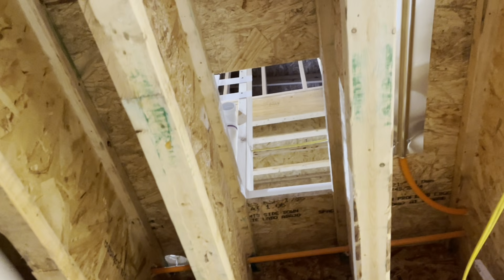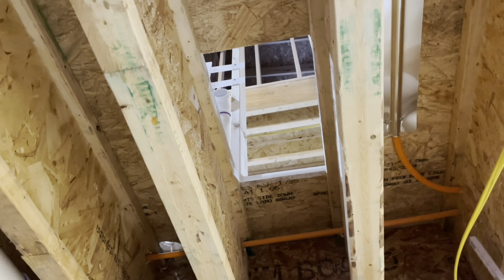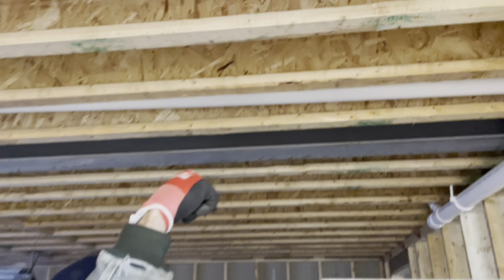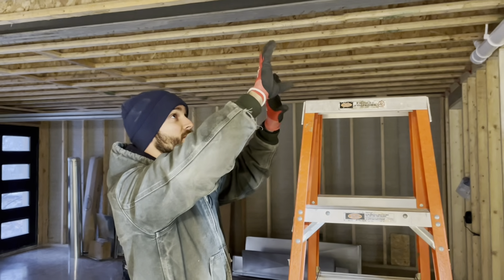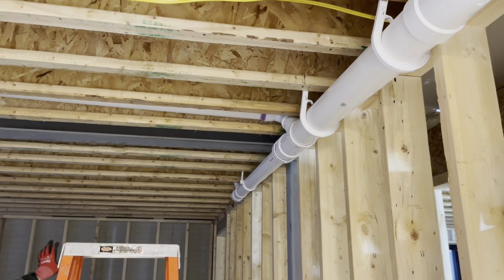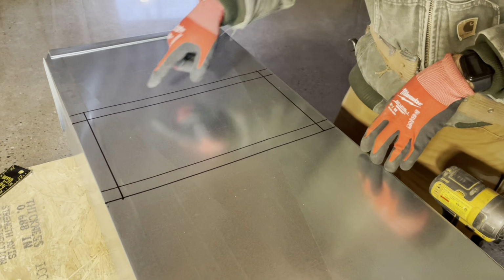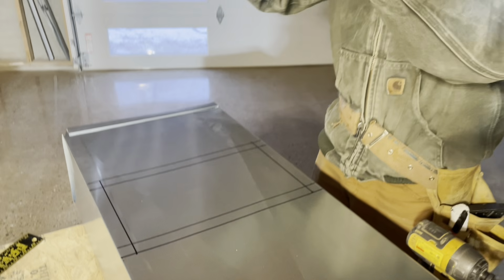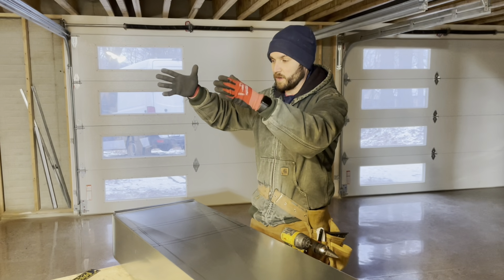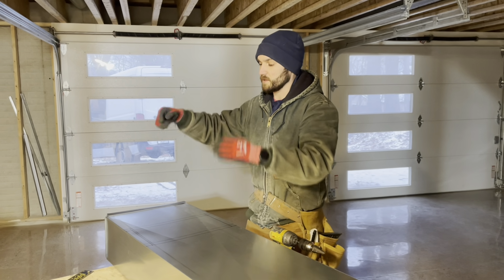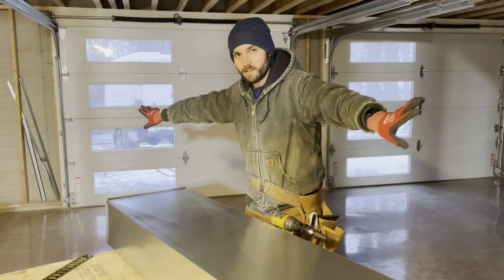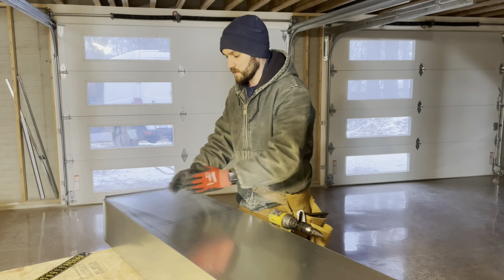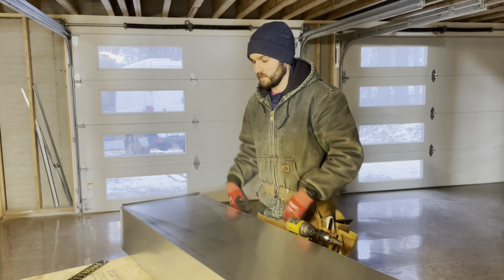Upstairs in the laundry room, we're going to have the air handler, which moves the air through the ductwork, forcing the air down. The trunk line is going to be right here, distributing air to all the branches. This is the first piece we're putting in. This hole matches the size of the one I cut in the floor, and the air handler will go above it, with some ductwork to adapt to it. It'll go down in here and then go that way. So I'm going to cut this out and bend some flanges up so I can adapt the plenum to it.